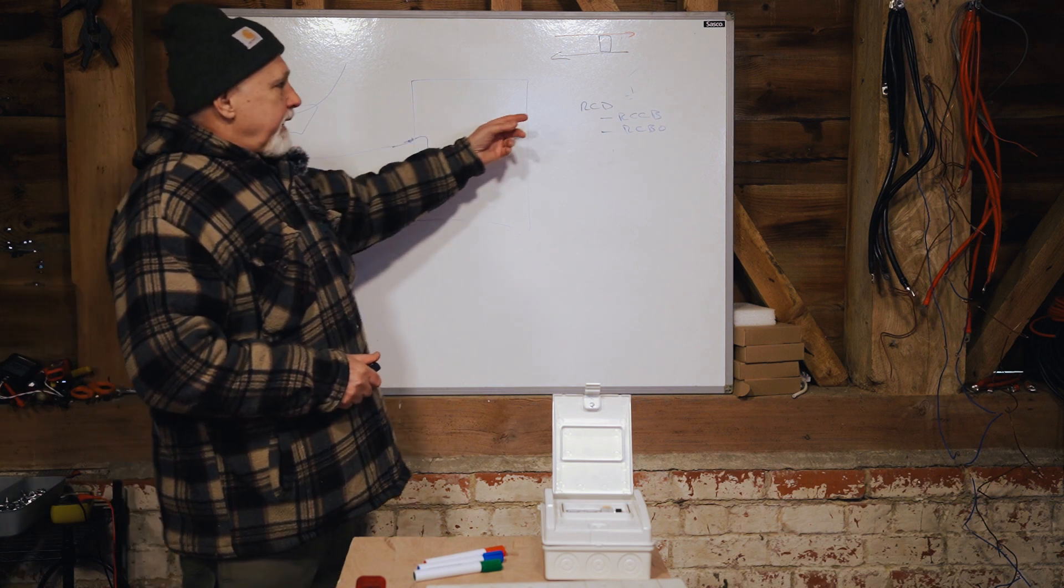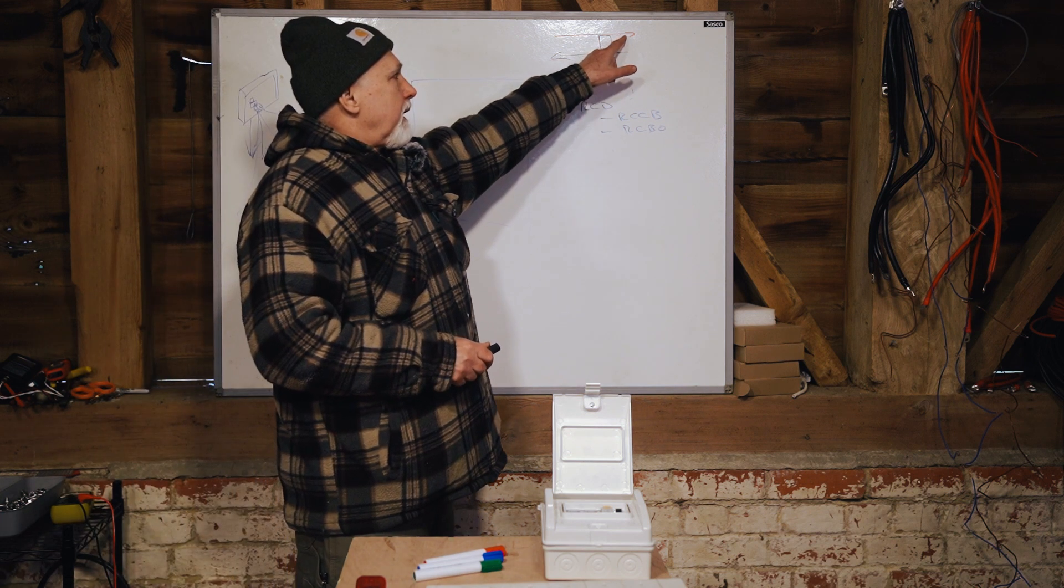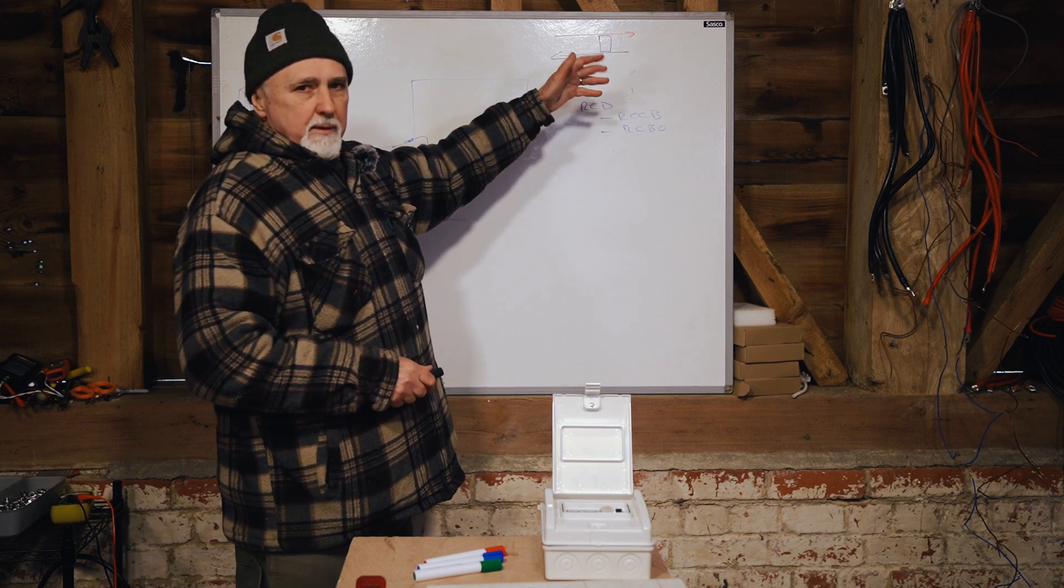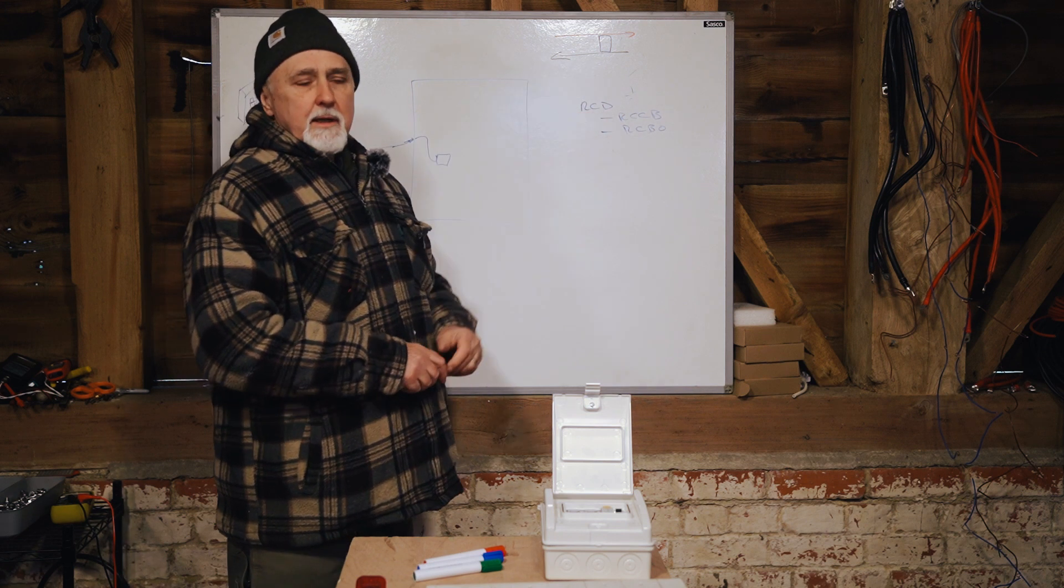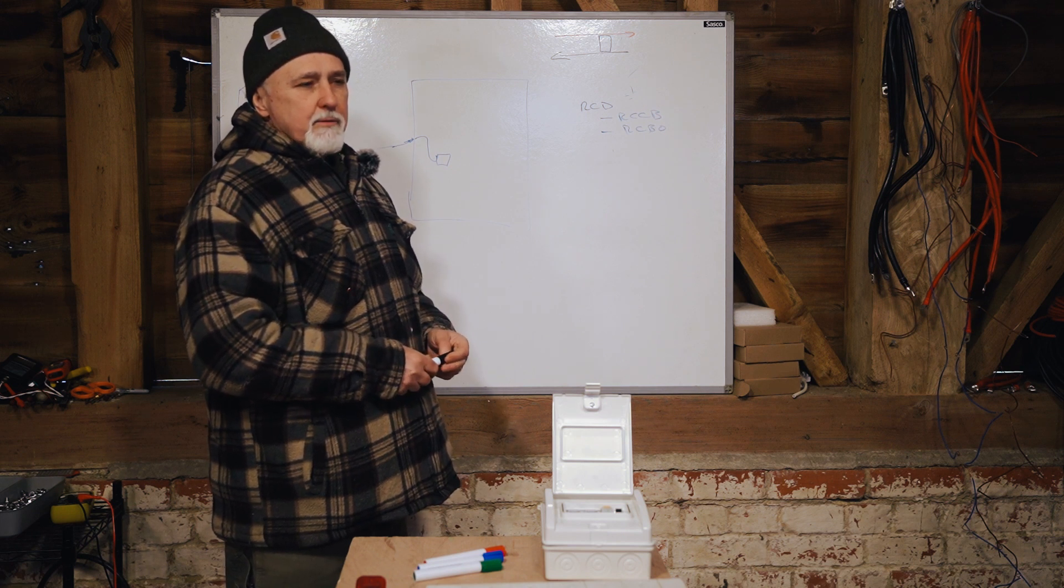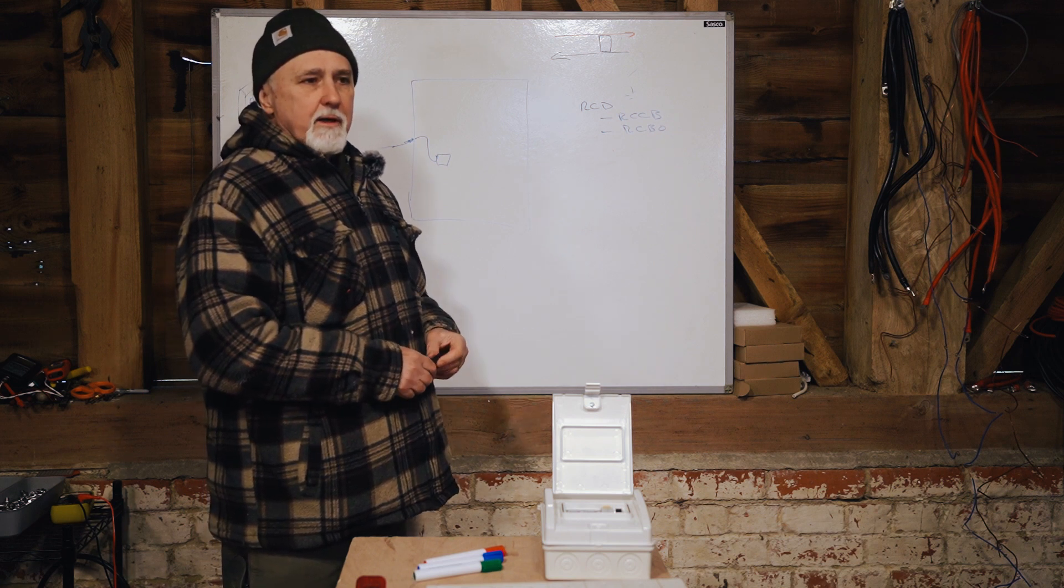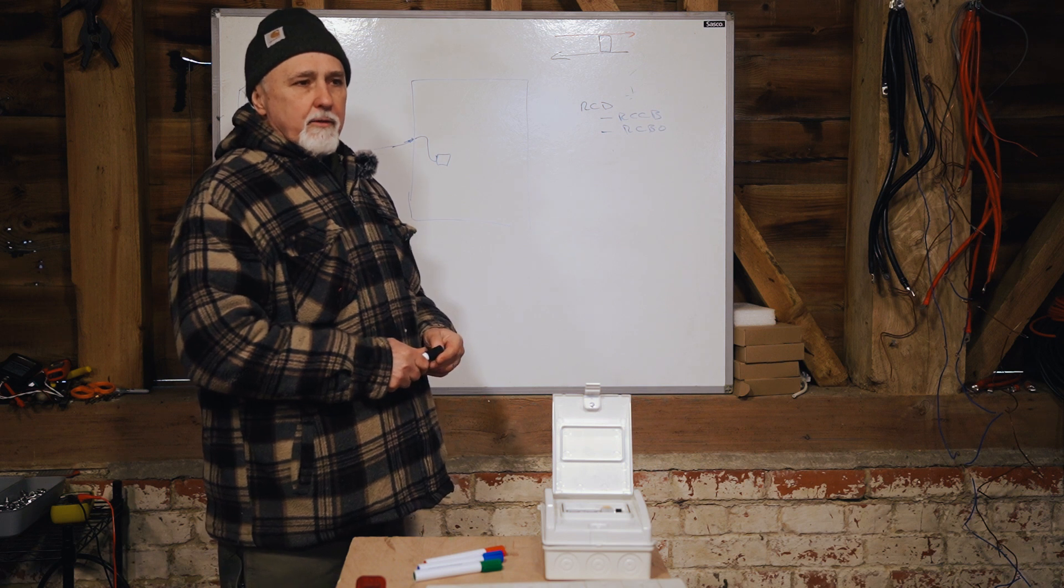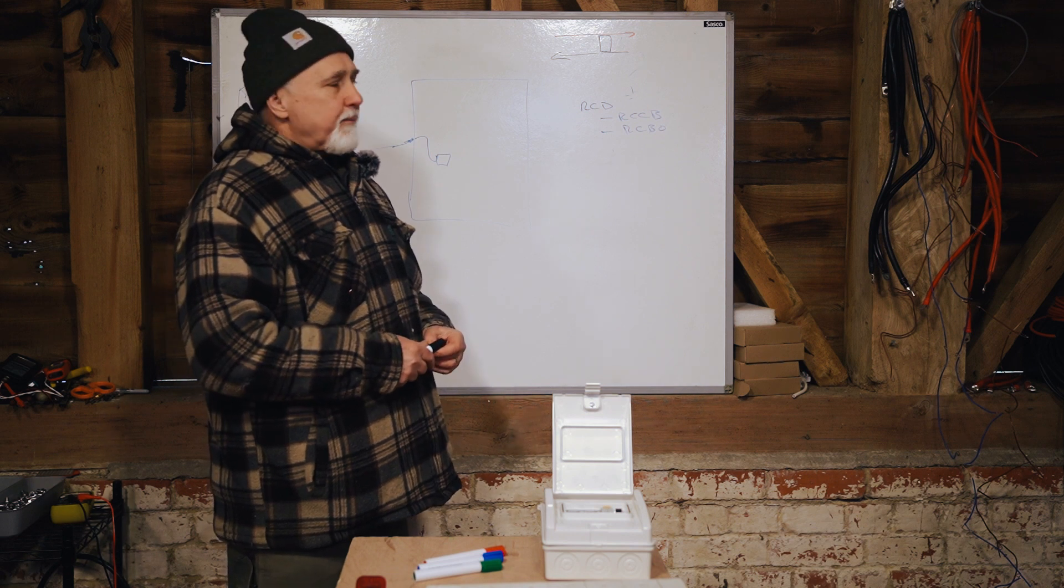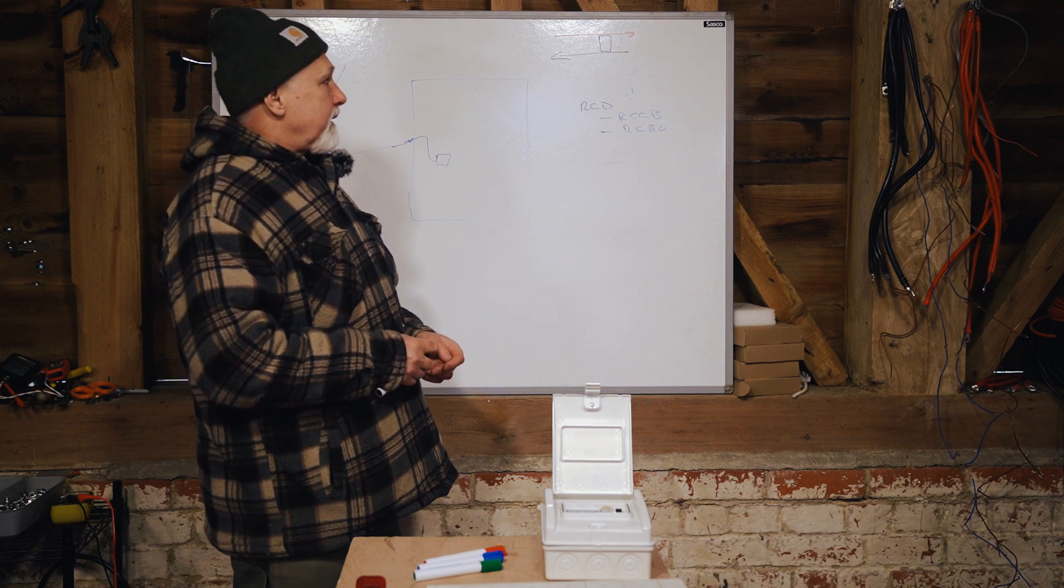The RCDs generally, there's a 30 milliamp trigger, so when it detects the difference between the live and neutral current of 30 milliamps, that's when it trips. There are other stipulations as well, but the important thing is 30 milliamps. And I can't remember exactly what it is, but there is a, I think it's around about 50 to 60 milliamps that it is thought that at that level it's enough to kill an average healthy adult human being. So 30 milliamps is well within that, and that is the normal RCD that you get in most places, is a 30 milliamp.